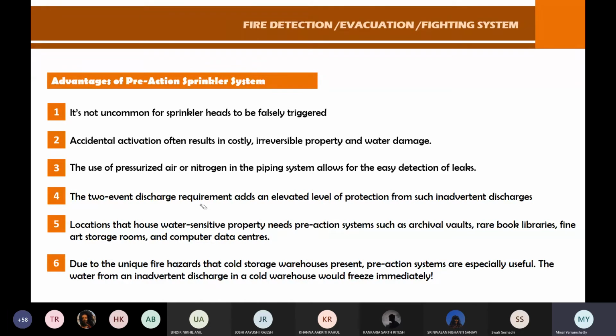Tremendous cultural loss. Rare book libraries, fine art storage rooms, computer data centers, anything sensitive that's computerized, or maybe even labs, certain labs doing important things, we don't know what goes on there. In such scenarios, you need to go for these kind of double lock systems. Due to the unique fire hazards that cold storage warehouses present, pre-action systems are especially useful there. The water from an inadvertent discharge in a cold warehouse would freeze immediately.